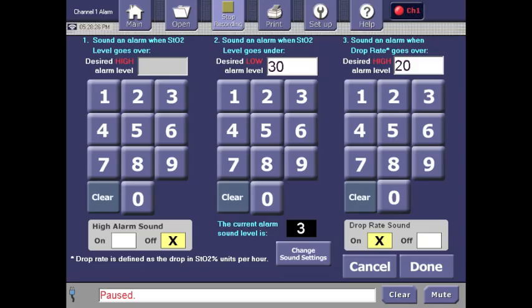It is recommended to monitor the patient for at least 48 hours post-operatively. During this time, there are 2 recommended parameters that are preset in the TOX monitor. The alarm will be triggered when the StO2 drops lower than the alarm line at 30% or has a drop rate of 20 points per hour. Alarm levels and drop rate settings can be changed in this menu and can be set differently at each channel if preferred. Remember, these are just the system defaults. Please refer to the surgeon instructions or hospital protocols.